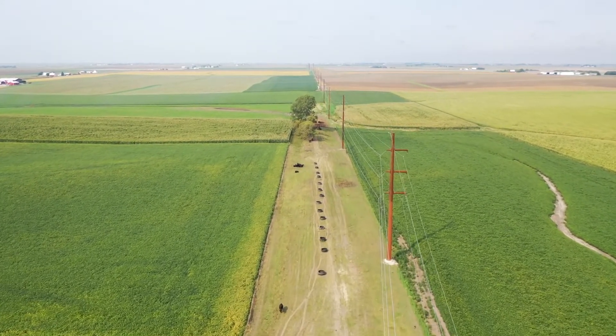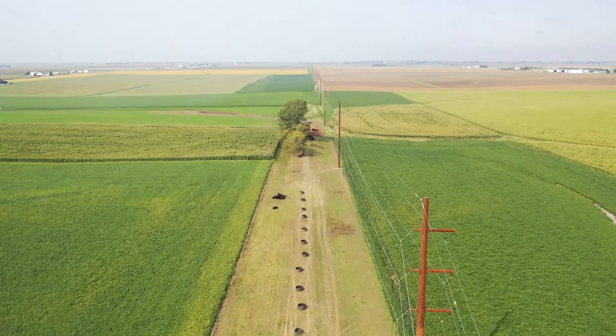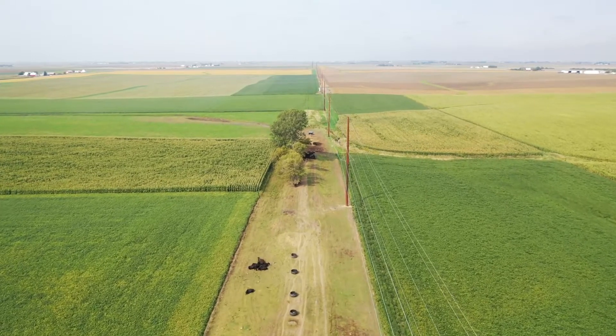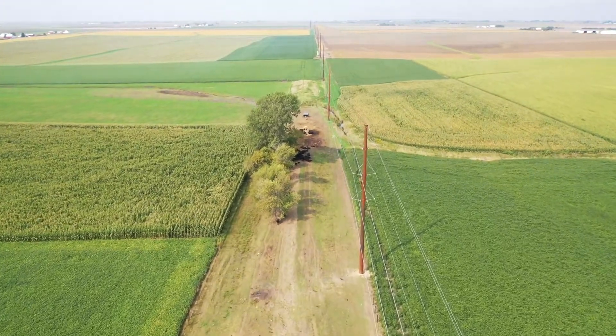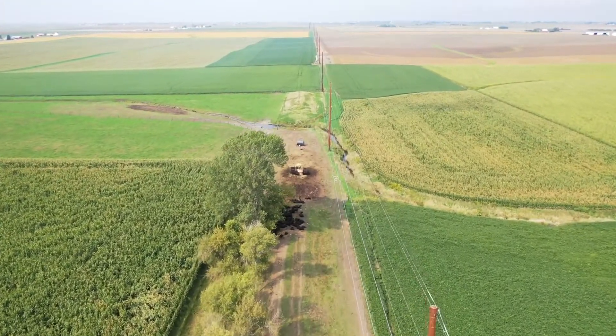After an engineering review of the line and the associated outages, it was determined that a complete rebuild was necessary to address the issues leading to increased outages. Among other design improvements, the new line was upgraded using tubular steel structures and incorporating conductor, insulators, and hardware to better withstand extreme weather conditions. This line has had quite a few problems over the years since it was built.